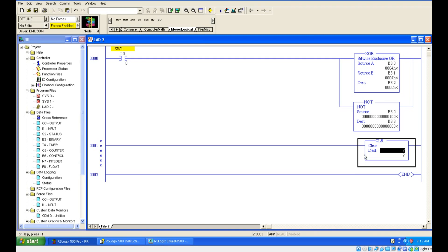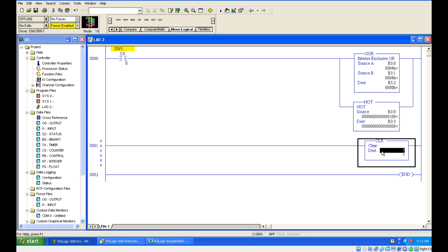If you see the instruction, it is having only one parameter which is called the destination. You need to give some address to this destination. Whenever the instruction is getting true condition, it will be clearing the data which is in that address. Cleared means what? It will refresh back to 0. If the data may be, imagine the data is having some 100. When the instruction is going true, whenever making the rung condition going true, it is making that 100 to 0.